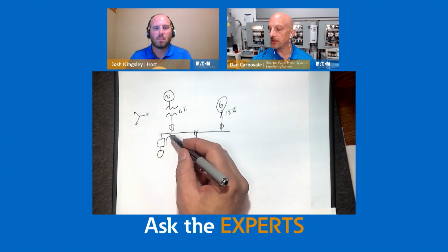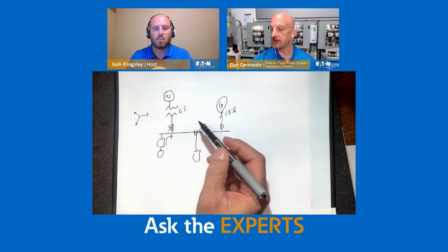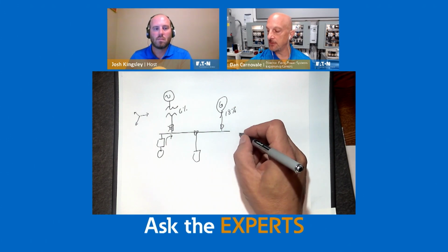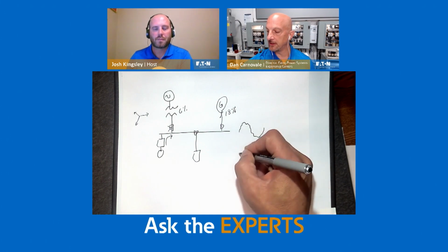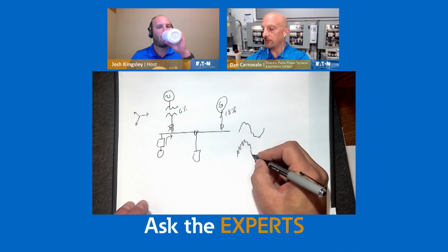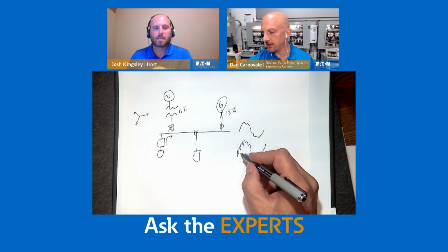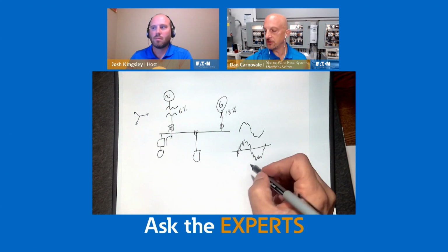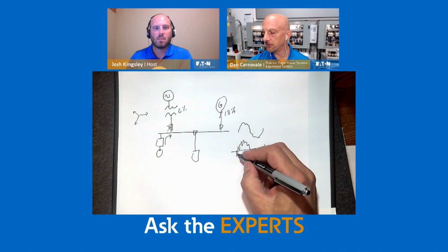But anyway, as we send the currents out, and then we switch over to the generator, so we take this out and we run over here to the generator, sometimes we'll have problems. Like I said, maybe we go from a voltage distortion that looks somewhat bad to something that looks horrible. And when I say horrible, I mean it could get really ugly pretty fast, because you've got 3 times the impedance. And what's that going to cause? You might actually have what we call multiple zero crossings. I'll explain a couple of scenarios with that, but you could have a bad voltage distortion. So by cleaning up the harmonics here, this goes back to normal.